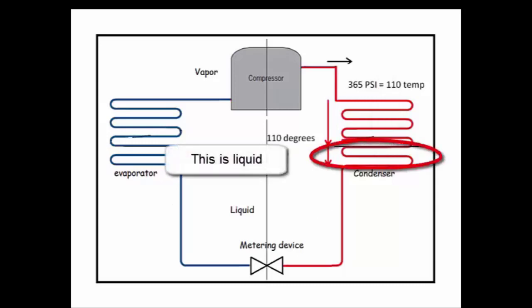Once it hits that black line, it's now all liquid. There's no vapor left. And from there to the bottom of the condenser, it will continue to give off heat and it gives off sensible heat. This liquid stacks up in the bottom of the condenser, waiting to exit the condenser and return to the evaporator via the liquid line.